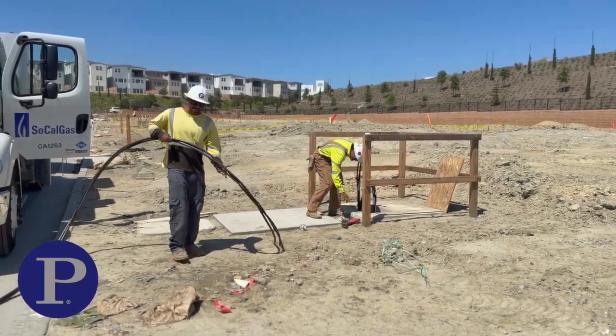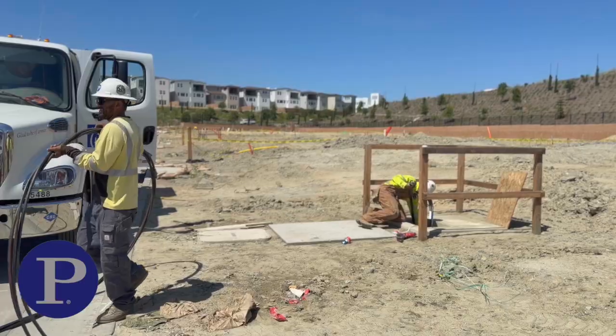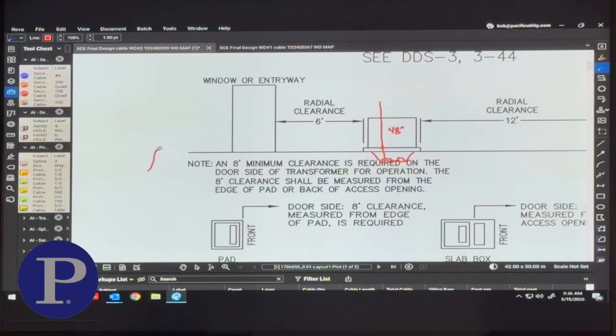Before the cable's cut. So if you're feeding into the transformer to a handhole over here, and you're feeding into the transformer and pulling it out of the handhole, you're going to wait until this cable is pulled up, measured perfectly, cut, and then this side you're going to leave 48 inches off of the top of the pad, and then cut right there at 48 inches.